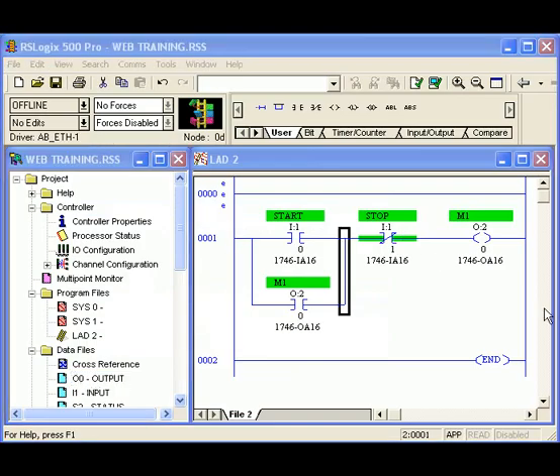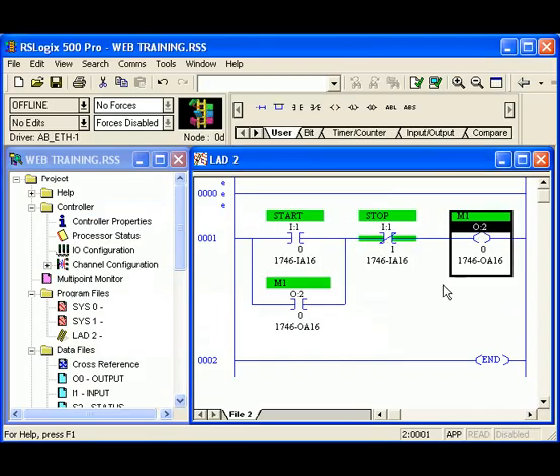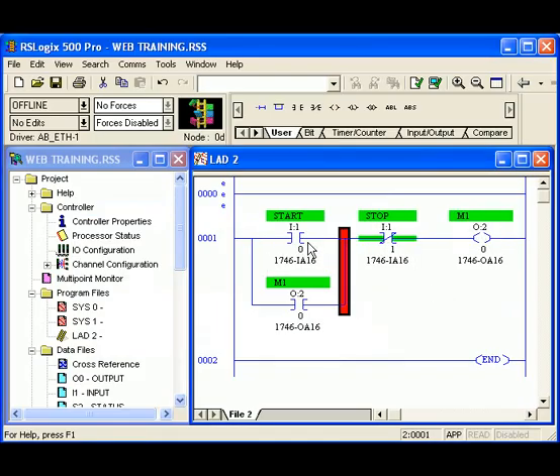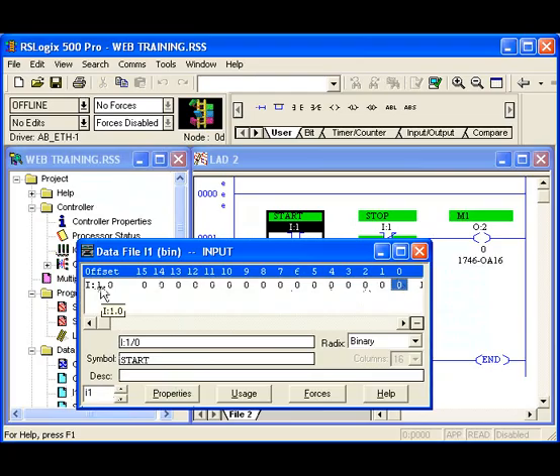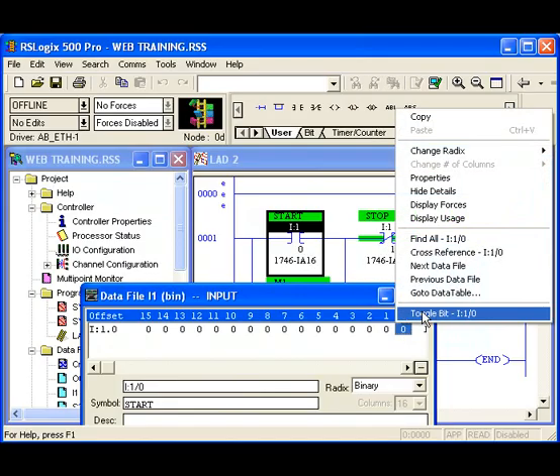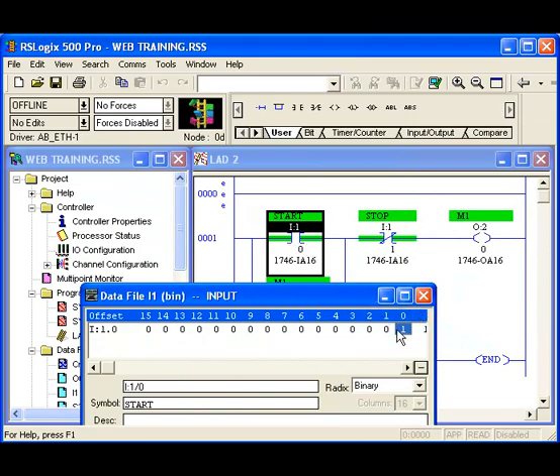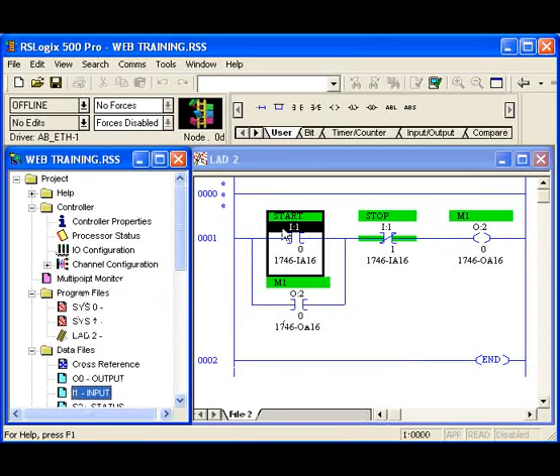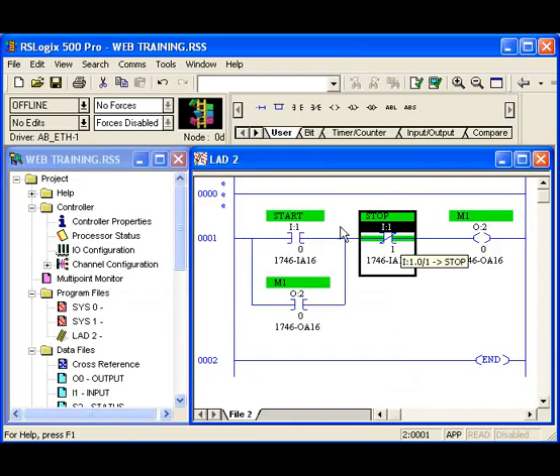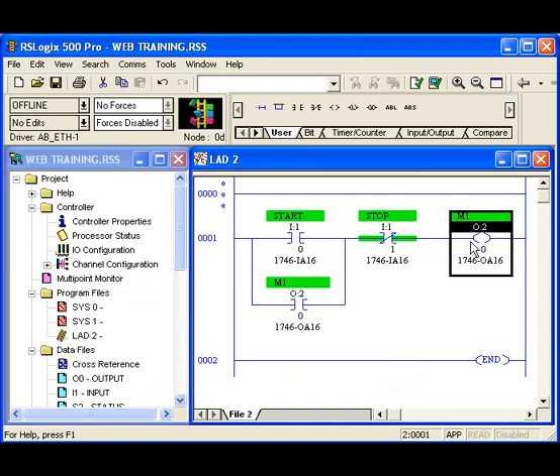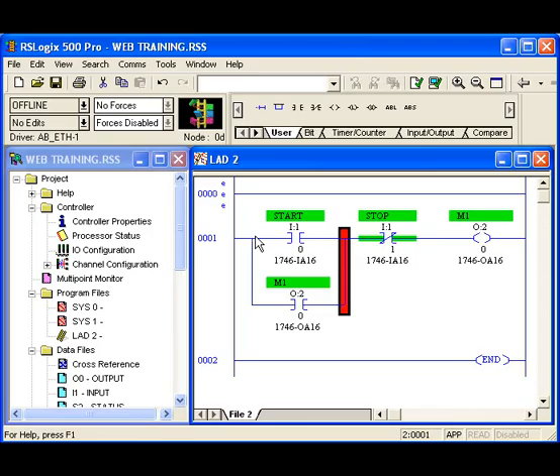Okay, now let's talk a little bit about what happens with our inputs and outputs in the program. You can see that we have inputs and outputs in our program here. These correlate directly with what we have in our data tables. This is I:1/0. This is I:1/0. That's the exact same bit. If I toggle this bit, you'll see a change in the program. So, this is how we get the input from the input card that we just added into our processor into our program. We also have a stop push button coming into our program. And we have an output going to the coil or the relay or contactor out in the field to be able to control our motor or other device.